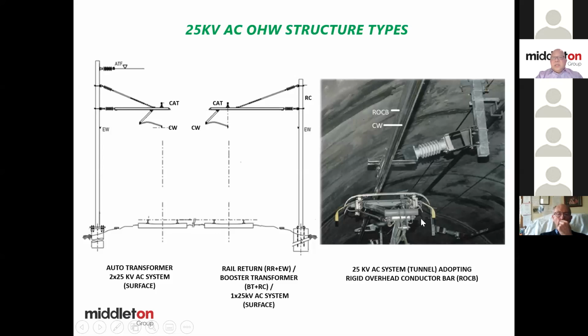And on the right-hand side here, this is what is called the rigid overhead conductor bar. You may hear somebody else use the term conductor beam or some other term or conductor rail, but they're all just different names. So basically you have an aluminum bar that is actually hollow inside, but a contact wire is clipped onto it. So the pantograph is actually making contact with the contact wire, not the aluminum. So together they can carry in excess of 3,000 amps, which is ideal. So you have the insulator there mounted to the soffit of the tunnel, yeah? The underside of the tunnel.